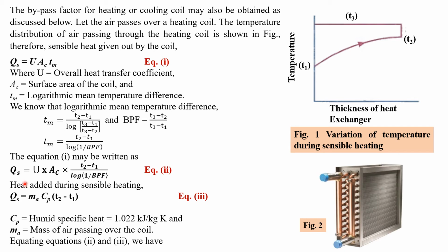So we know that the heat added during the sensible heating is equal to m Cp delta T. So Qs is going to be the mass flow rate of the air multiplied by its humid specific heat and multiplied by the temperature rise it undergoes during the heating process. Here the Cp is the humid specific heat. Its value is 1.022 kilojoules per kg Kelvin, and Ma is nothing but the mass of the air passing over the coil. So now we can equate equation number 2 with equation number 3.